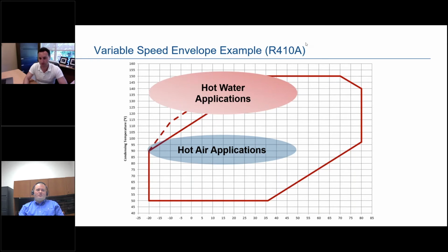This is really reiterating the typical variable speed envelope. You can see this is R410A, like we said earlier. You can see hot air applications. Really, this envelope can do pretty well anytime you want to make hot air, really heat pump systems. You don't get the extra efficiency or capacity out of just a variable speed non-injection compressor, but you'll still be able to operate there.